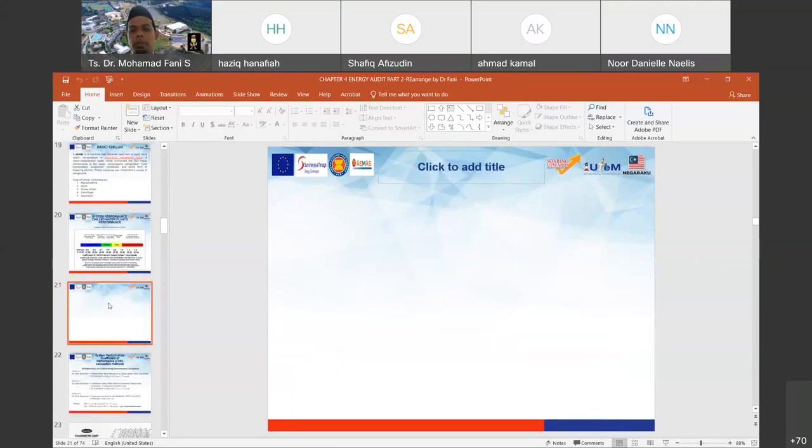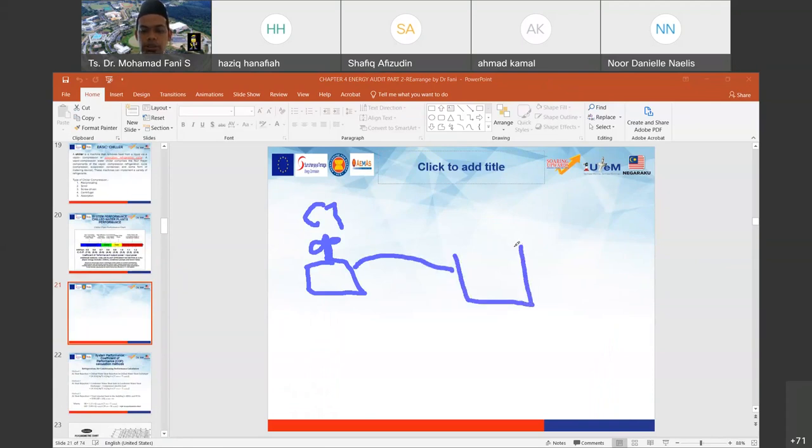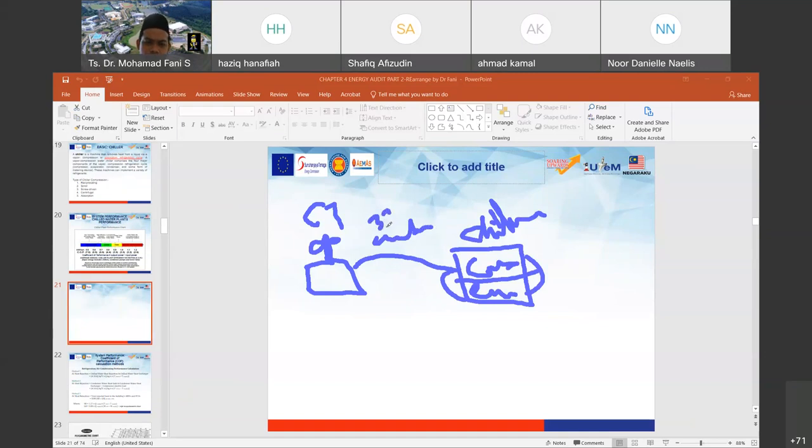I actually need to draw this, the chiller plant. Okay, the chill water types, basically they will have the CT here, cooling tower. Okay, cooling tower to supply condenser water to the chiller. This one chiller, we have condenser and evaporator. Okay, so this is the process inside the chiller.